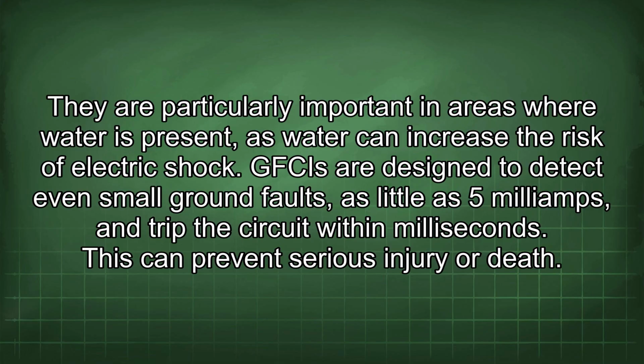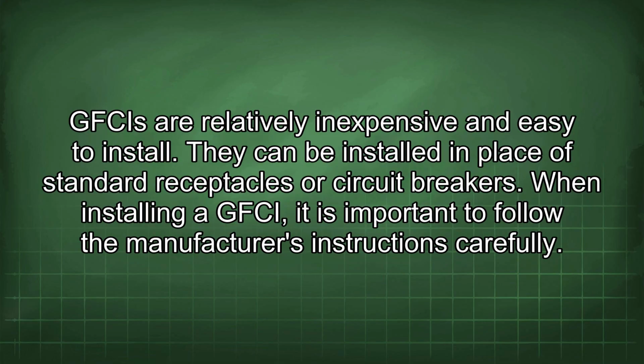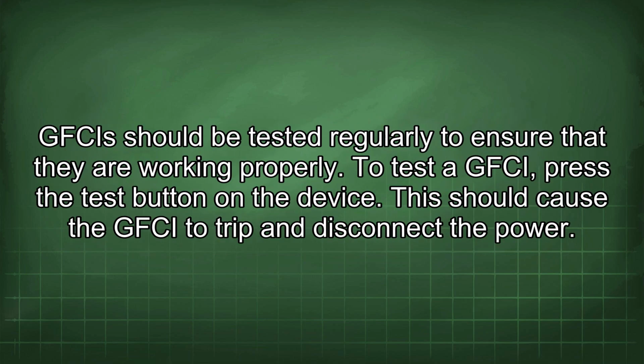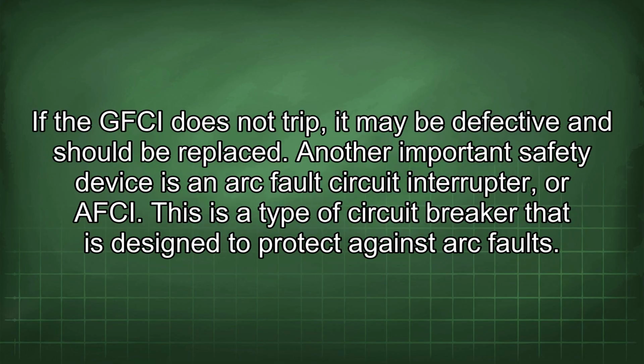GFCIs are designed to detect even small ground faults, as little as 5 mA, and trip the circuit within milliseconds. This can prevent serious injury or death. GFCIs are relatively inexpensive and easy to install. They can be installed in place of standard receptacles or circuit breakers. When installing a GFCI, it is important to follow the manufacturer's instructions carefully. GFCIs should be tested regularly to ensure that they are working properly. To test a GFCI, press the test button on the device. This should cause the GFCI to trip and disconnect the power. If the GFCI does not trip, it may be defective and should be replaced.